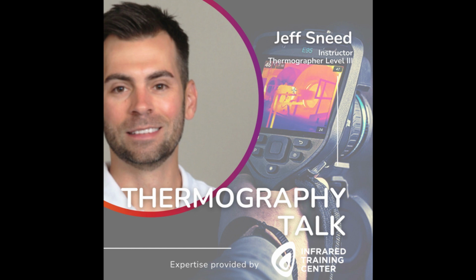Categories 3 and 4 are basically the same clothes, the same type of material. The difference is the rating on the clothes: they're thicker, and the materials they're made from could potentially be a little different depending on the manufacturer. A category 3 suit is rated 25 calories and a category 4 is rated 40, even though the clothes look exactly the same. So if you have both a 3 and a 4 suit, make sure you grab the proper one for the job. If you need the 40 cal suit, make sure you grab the category 4 suit. These are things to think about — which cabinet you'll be working in requires a different level of clothing.